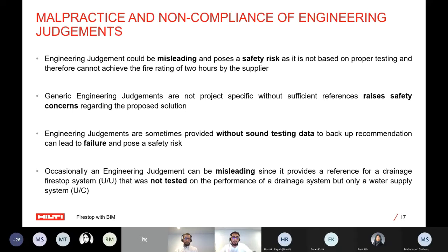Now, when we were talking about the different items that we need to consider for fire stopping, we said that we need to take into consideration, for example, if it's a PVC or a PPR pipe and the different dimensions. But something that is very critical as well is whether this pipe is pressurized or filled with water, or if it's a non-pressurized pipe, an open piping system, so basically it does not have continuous water running through it. The tested and approved solutions for these cases are extremely different. So for an open piping system, for example, you might require a much stricter fire stopping material for it to operate properly and give you the 2 hour fire rating. So it's also very important to keep in consideration what these engineering judgments consist of and for what application they are being used. So for example, is it for a water supply pipe or is it for a drainage pipe as well? Does it work as well? So all of these are the different considerations that you might take.